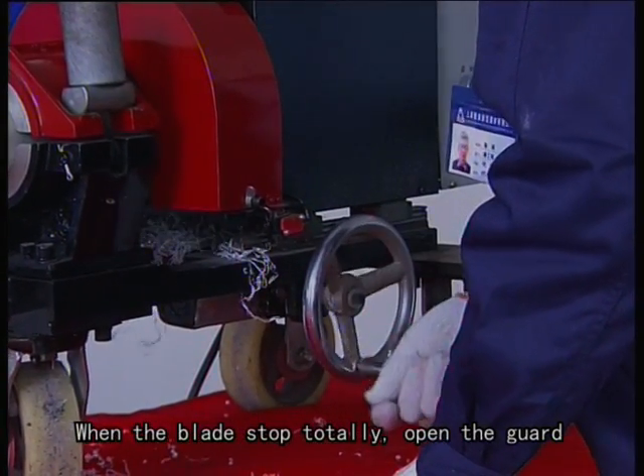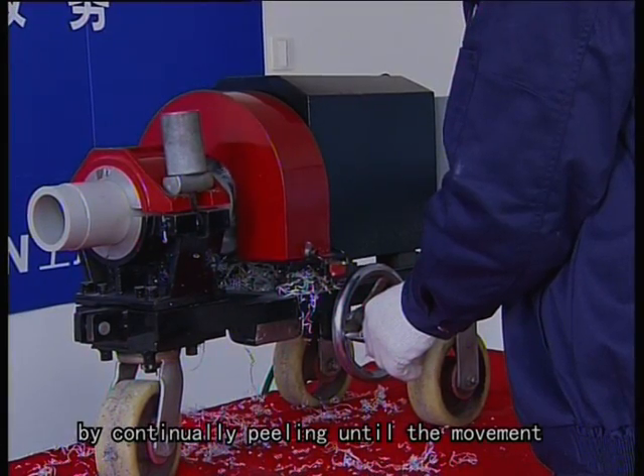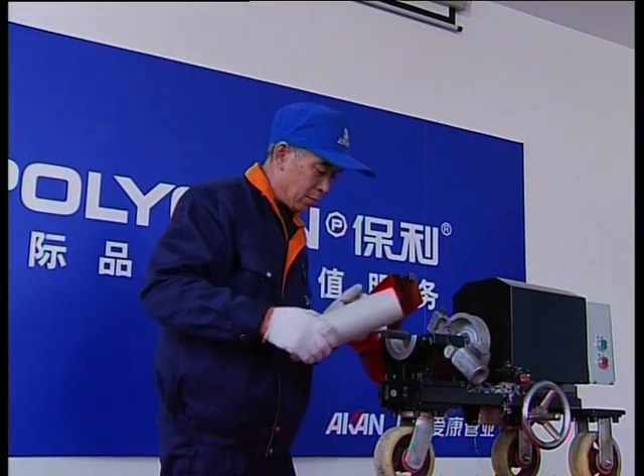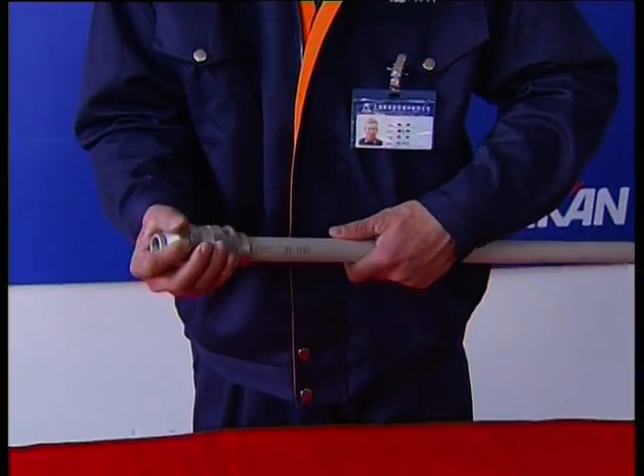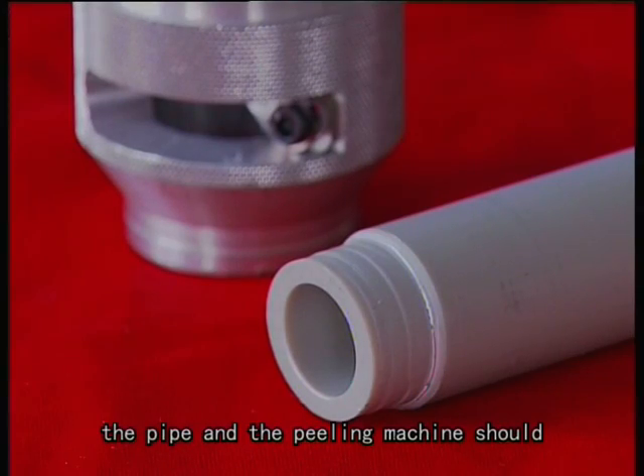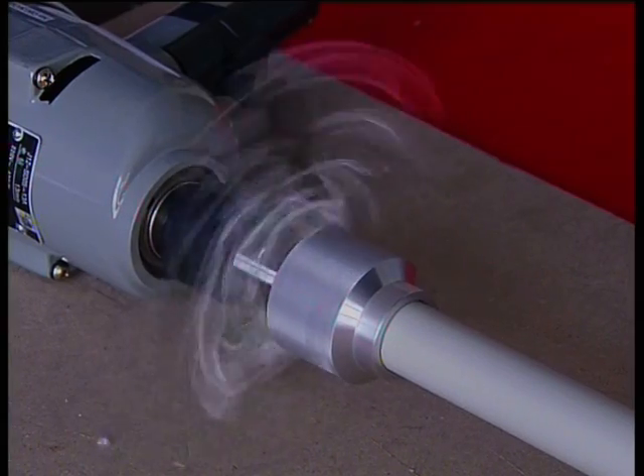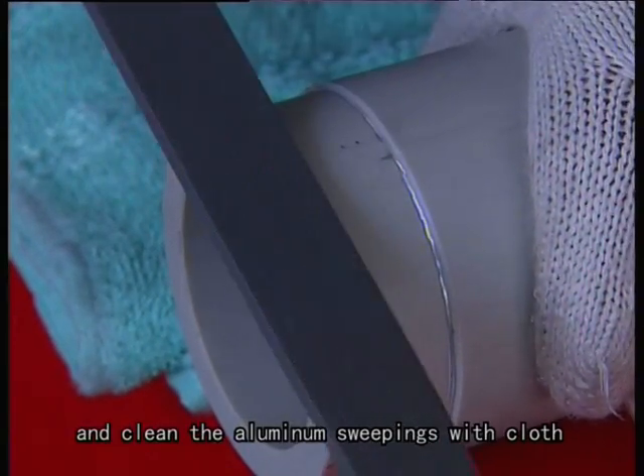When the blade stops rotating totally, open the guard. For manual peeling, ensure enough peeling length by continually peeling until the movement cannot go on. As the electric motor's rotation speed is very fast, the pipe and the peeling machine should be kept on the same axis before peeling to ensure accuracy. When meeting leftover aluminum foil, use the flat file to remove it and clean the aluminum sweepings with a wiping cloth.